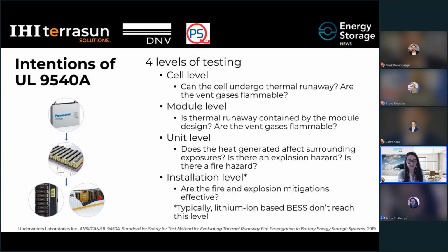At the cell level, can the cell undergo thermal runaway? Are the vent gases flammable? At the module level, is there thermal runaway, or is the thermal runaway contained by the module design? Again, are the vent gases flammable? At the unit level, does the heat generated affect the surrounding exposures? Is there an explosion hazard? Is there a fire hazard? And at the installation level, are the fire and explosion mitigations effective? Typically we do not see installation level tests because lithium-ion based batteries at least don't reach this level.